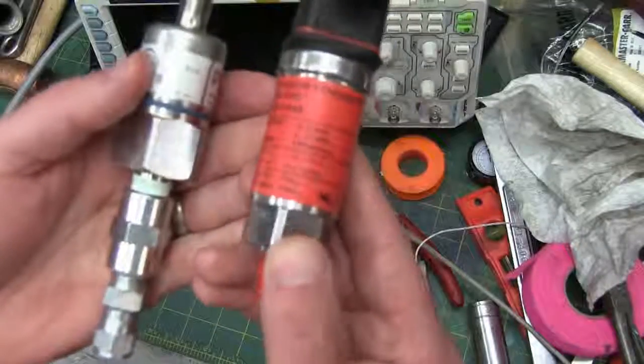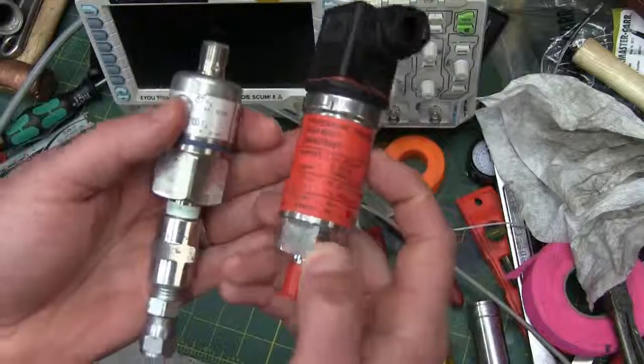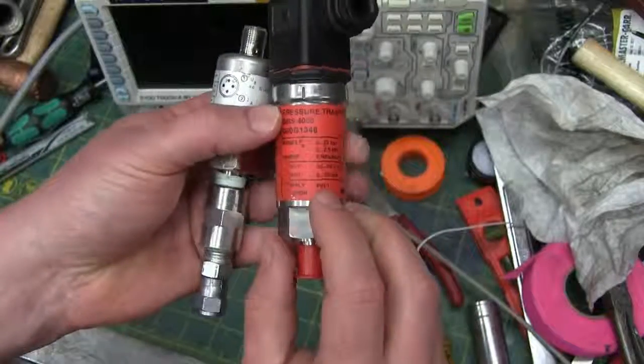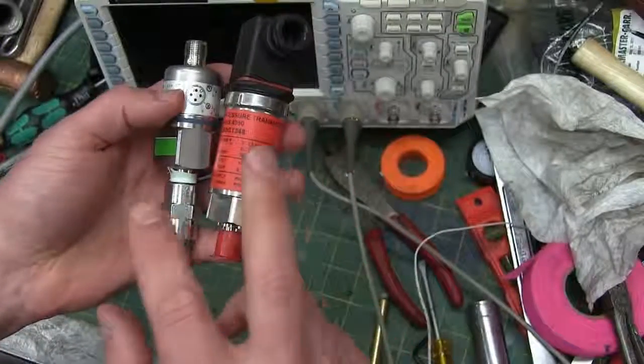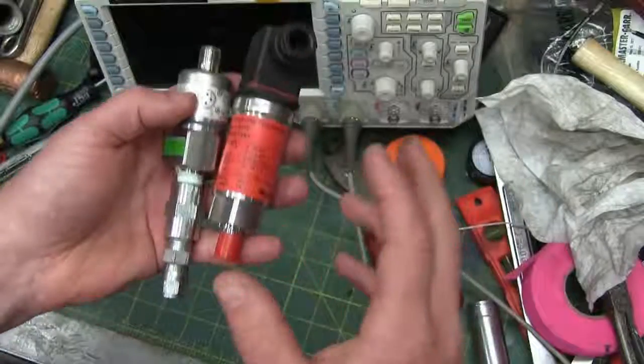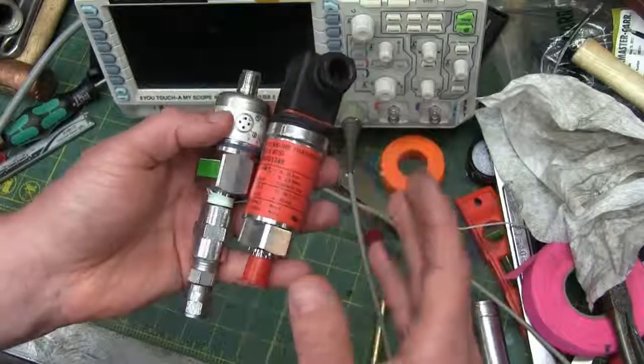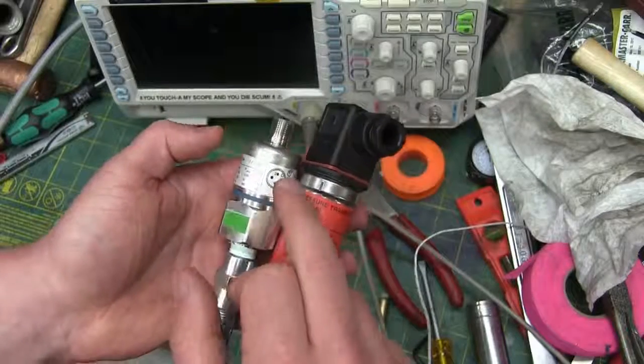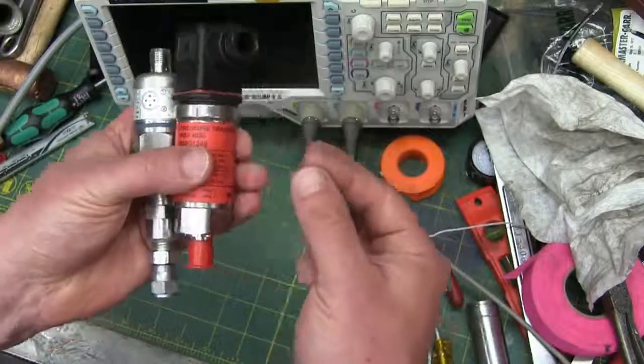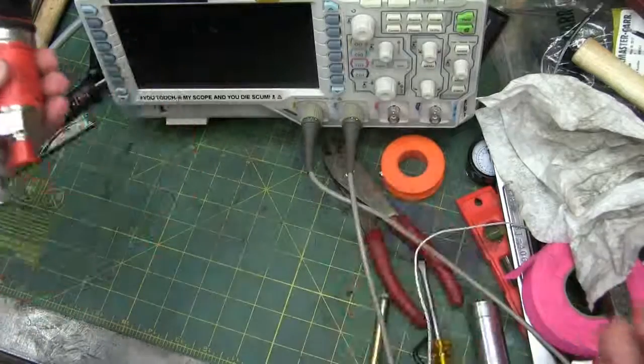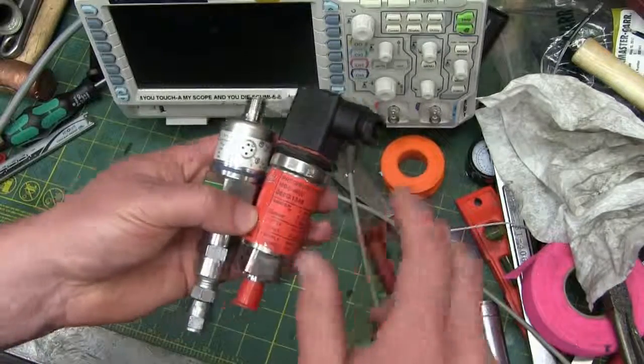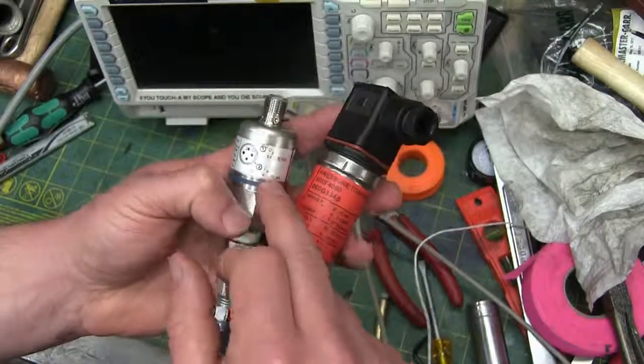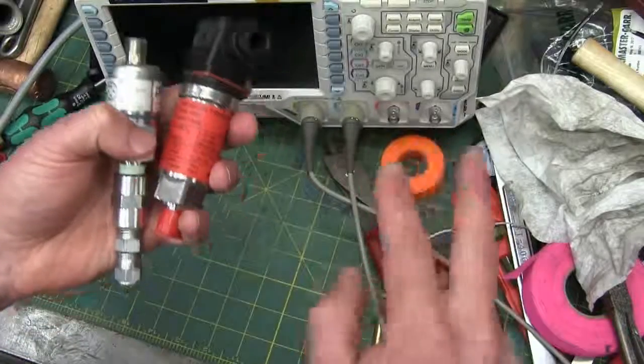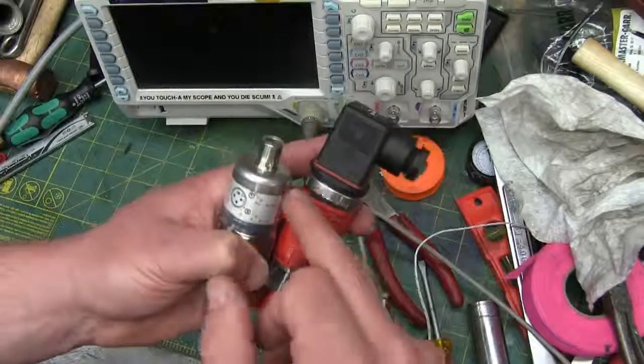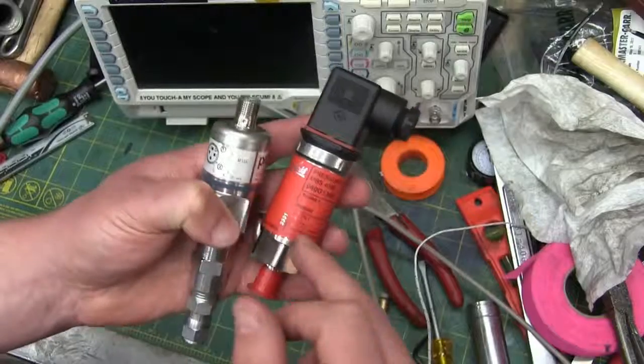So the difference between this one, this is a current loop device as well. But the difference between analog voltage out, the 0 or 0.5 volts to 5 volts, is that these are less susceptible to noise and also less susceptible for longer runs of instrumentation cable, less susceptible to voltage drop. So these are quite a bit more robust, but there's a little bit of fancy two-stepping we got to do in order to use that for the Arduino.